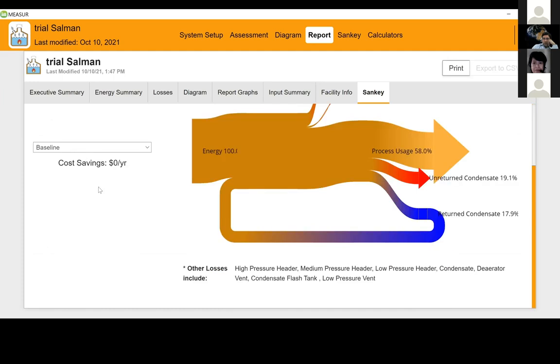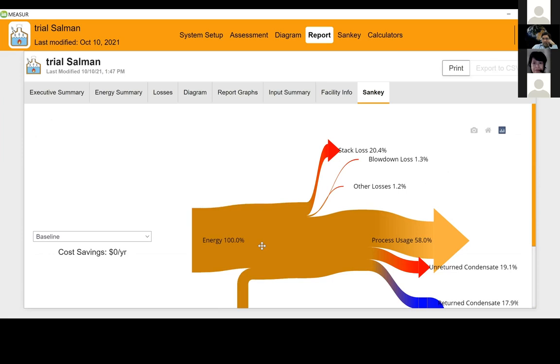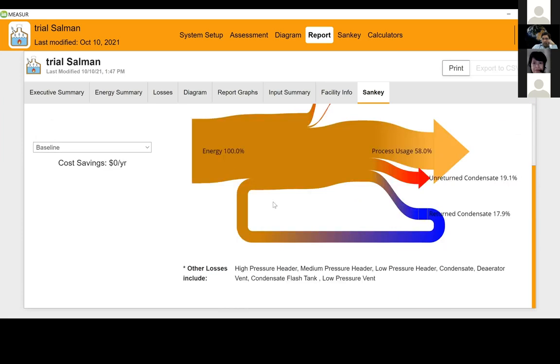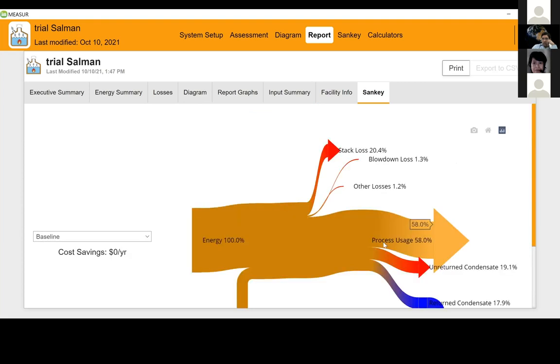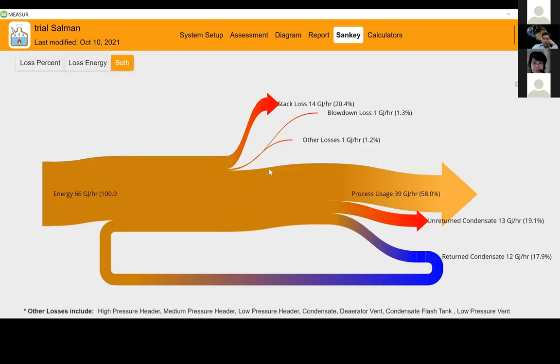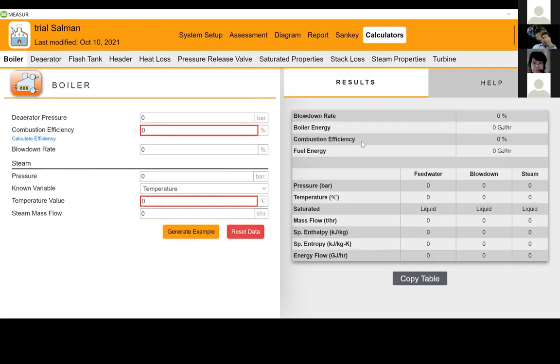So because we only did this assessment for the baseline, it provides us the Sankey diagram only for the baseline. It shows you how much total energy is going in and where is it being used. So process usage, unreturned condensate, returned condensate, blowdown losses, other losses, stack losses, all put there together. And if we click print, all these sections get printed into a report form. This Sankey also shows on top in the Sankey section. And if you go to calculators, you can have multiple calculators there. So you can do a calculation for boiler, deaerator, flash tank, header, heat loss. So all the data that we put there, if we don't have the data, we can also do a calculation here as well. So a wonderful tool, I really like it.